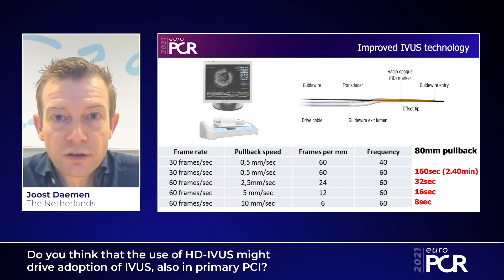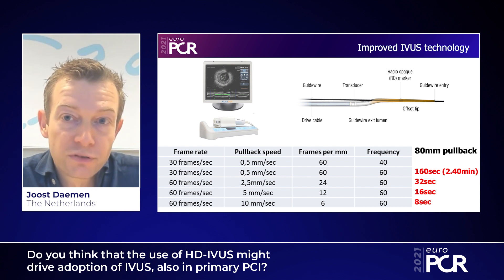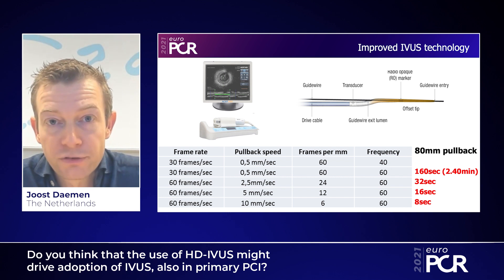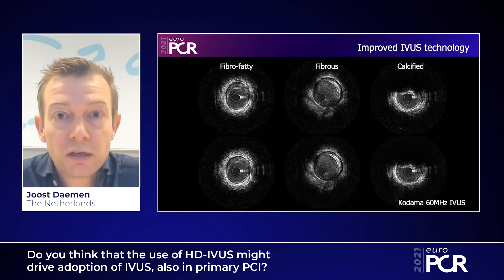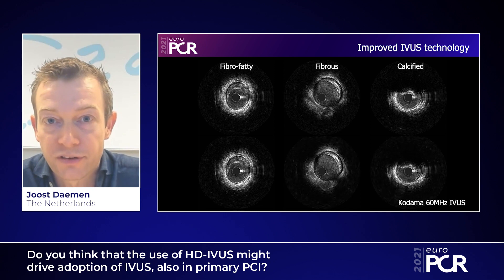Newer IVUS technologies, like those used in the SPECTRUM trial, may help drive adoption of IVUS in STEMI patients for two reasons. First, novel technologies like the ACIST Kodama IVUS catheter with a broadband transducer at 60 MHz provide very good radial and axial resolution, facilitating image interpretation — making identification of plaque, thrombus, and dissections considerably easier compared to initial 20 MHz systems.